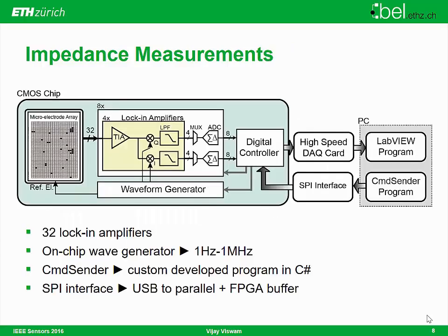Thirty-two of these Lock-in Amplifiers are integrated on-chip. There is also an integrated waveform generator which generates frequencies from 1 Hz to 1 MHz, which is applied to a reference electrode around the microelectrode array. The analog output is digitized using a Sigma-Delta converter, and a high-speed data acquisition card from National Instruments sends the data to a PC running a LabVIEW program for visualization. There is also a command interface that uses a serial peripheral interface to communicate with the chip from the external world.